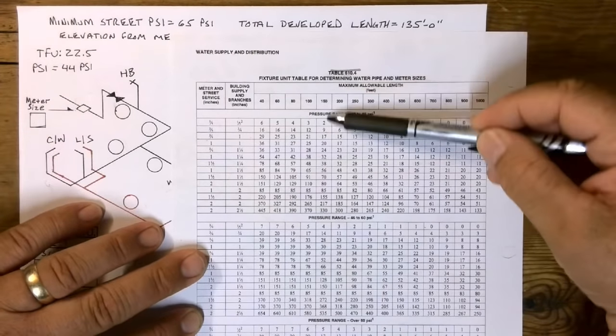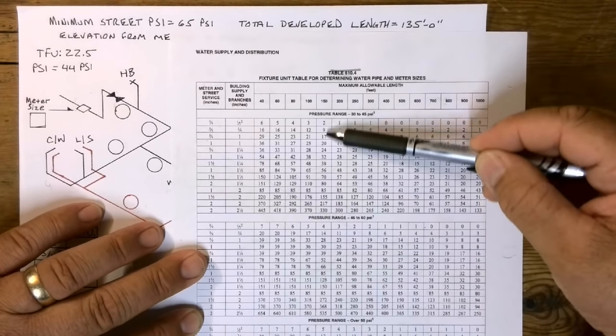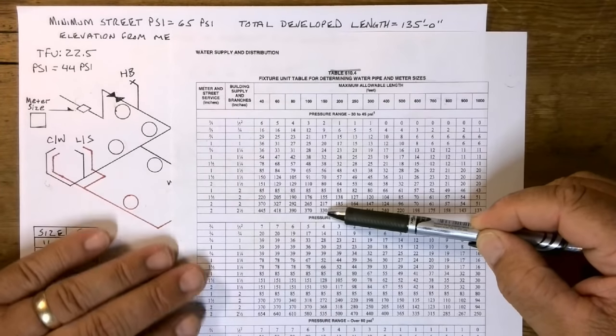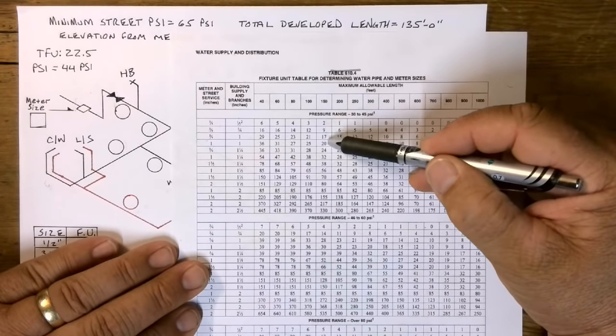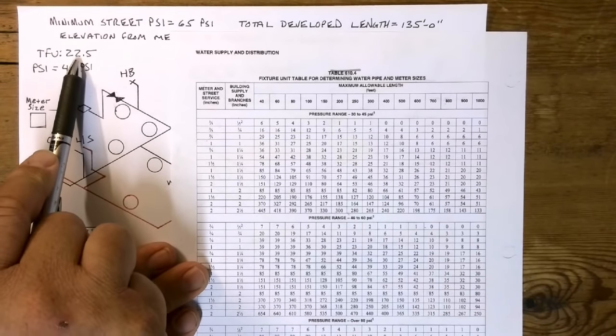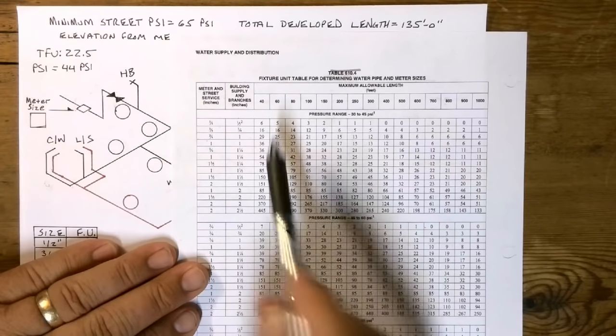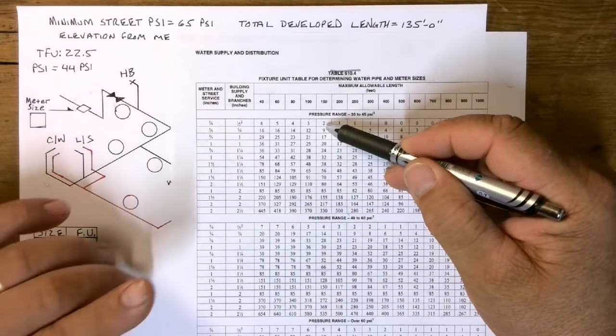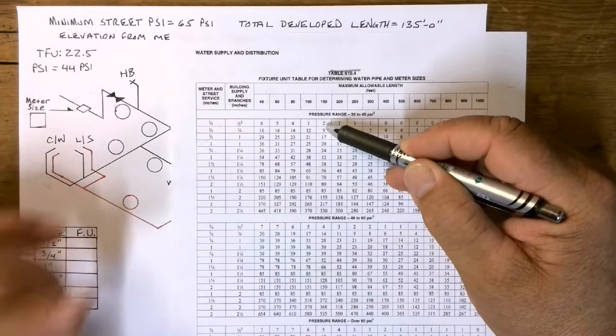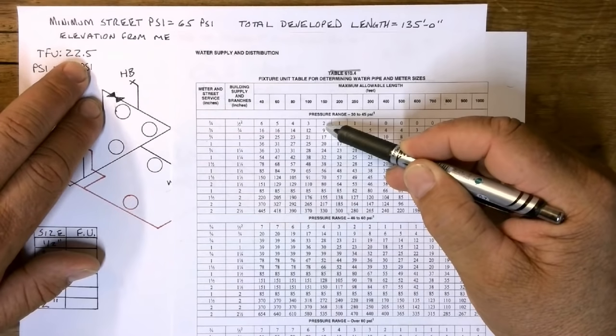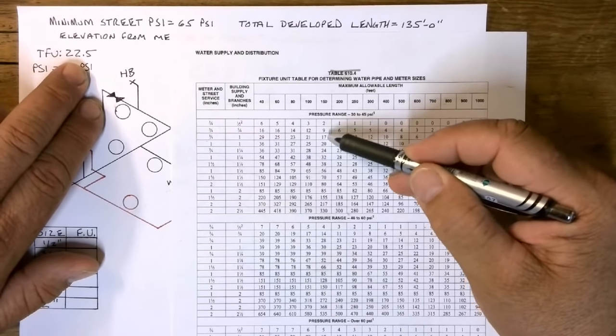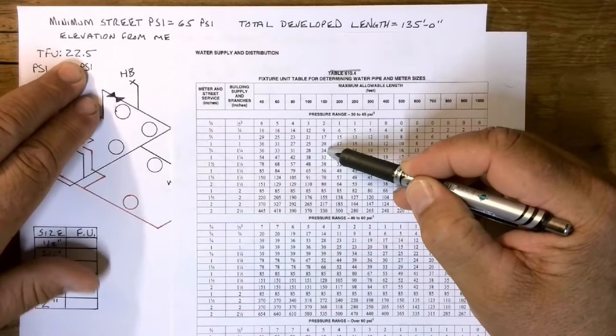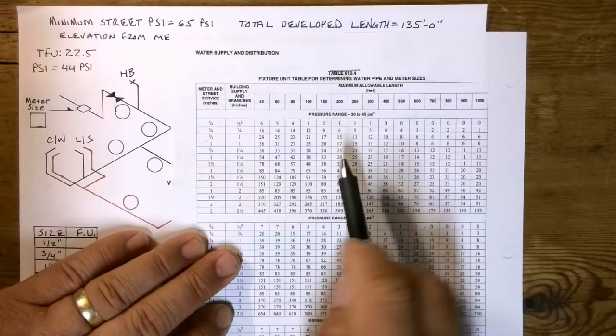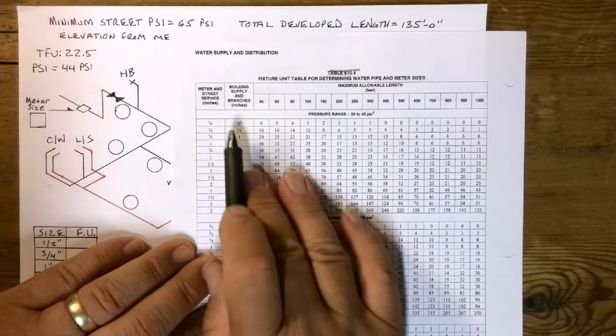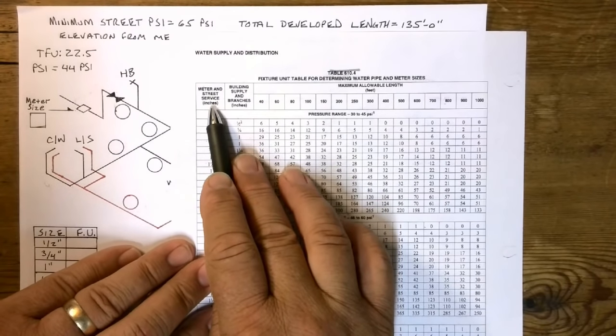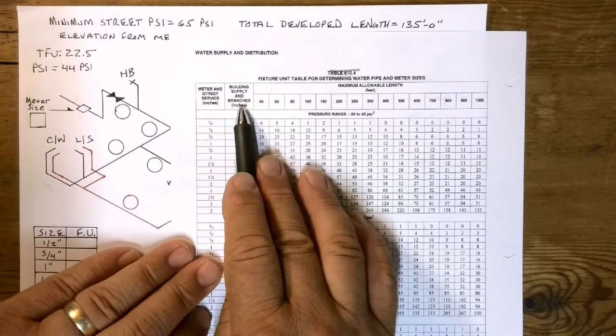So this is my column right here. These numbers I run off of. I'm going to go down the 150 column until I hit a number that is either equal to or greater than my 22.5 fixture units. Okay, 2, 9, 17, 20, 24. 24 is the one. Winner, winner, right? So we're going to take 24, and from here, look at this. I have meter and street service, so that's my water meter, and that's my building supply.